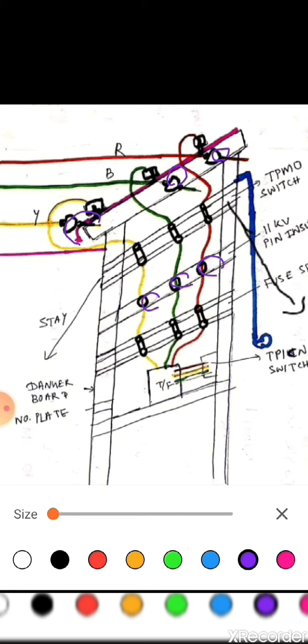Next one is binding wire. As I have already told, the binding wire is used to bind the insulator with the transmission wire. So for this insulator, the binding wire is required, and the quantity is 500 gram. Next we require number plate. To recognize the substation, we have to give the number. So number plate is 1. Next is danger plate. So danger plate is required. Next is barbed wire. Barbed wire is required to stop the climbing of unauthorized persons. Next one is earthing. One set of earthing is required for this substation.